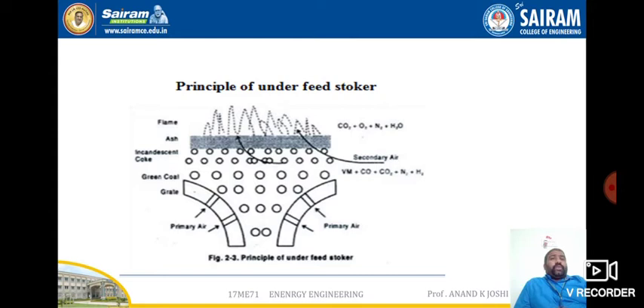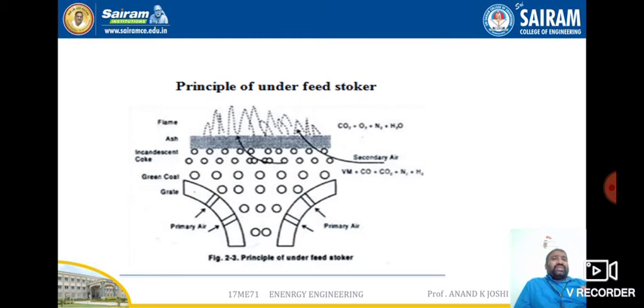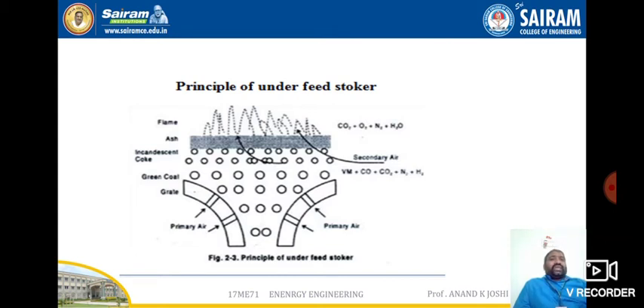The next topic is the principle of the underfeed stoker. In the underfeed stoker, coal is admitted into the furnace below the point of air admission. Both air and coal fuel move in the same direction. Because of this, it is suitable for burning semi-bituminous and bituminous types of coal. The combustion mechanism of the underfeed stoker can be explained as follows: air enters through the holes in the grate, meets the green coal, and diffuses through the bed of green coal, meeting the volatile matter produced by the green coal.